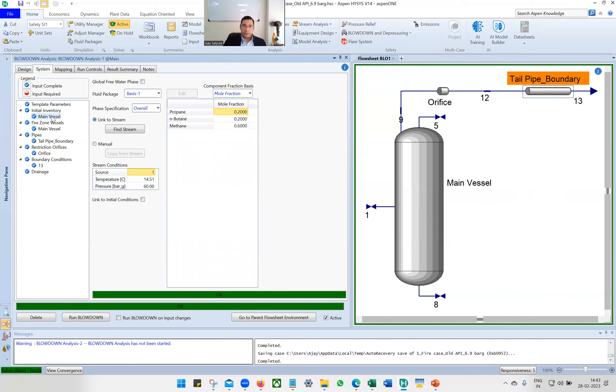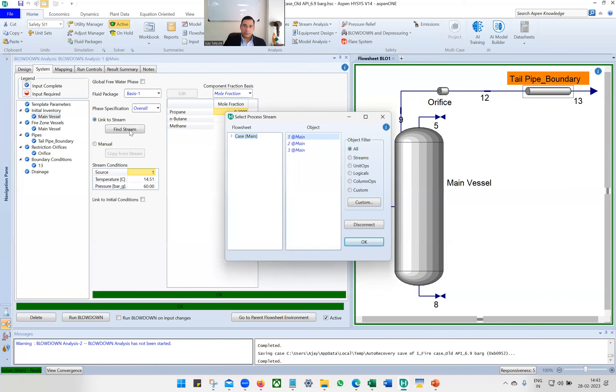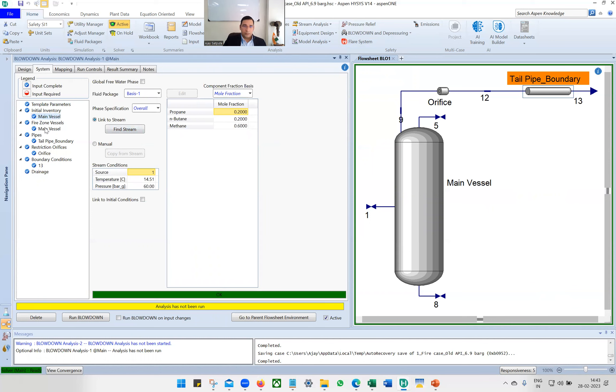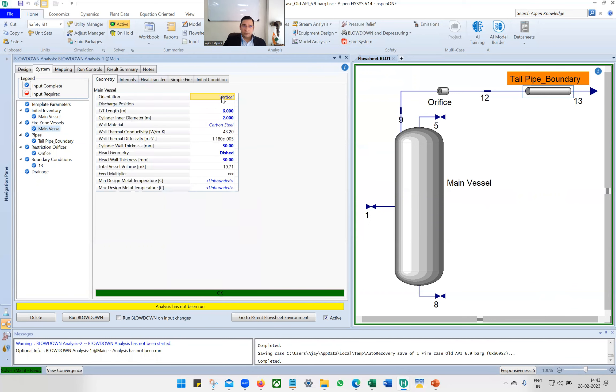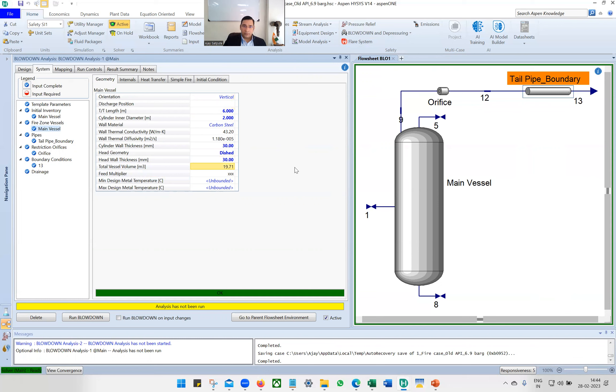Go to Main Vessel. Select Link to Stream and find stream one — the inlet to the separator — and click OK. Then go to Fire Zone Vessel and set the geometry. It is a vertical vessel, tan-tan height 6 meters, diameter 2 meters. Cylinder wall thickness is 30 mm — slightly more than 1 inch. Head geometry is dish, head wall thickness 30 mm. The vessel volume comes out to approximately 20 cubic meters.